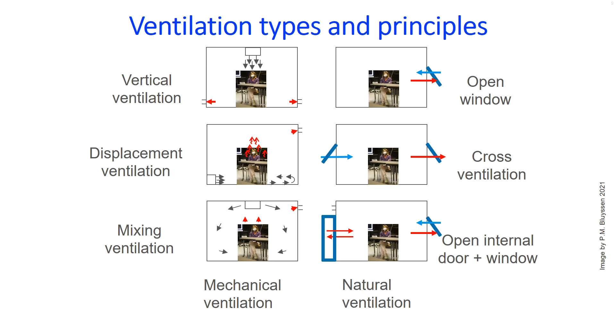Last but not least, ventilation is used as a control strategy for indoor air quality. Ventilation can be established by simply opening a window — natural ventilation — or by using a mechanical ventilation system, ranging from exhaust-only to very advanced air conditioning systems that both supply and exhaust air. Mechanical ventilation gives the possibility to control the amount of air supplied and exhausted, while natural ventilation, such as opening a window, is an uncontrolled and therefore less reliable method.